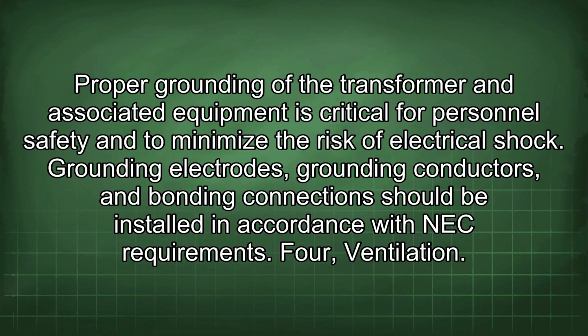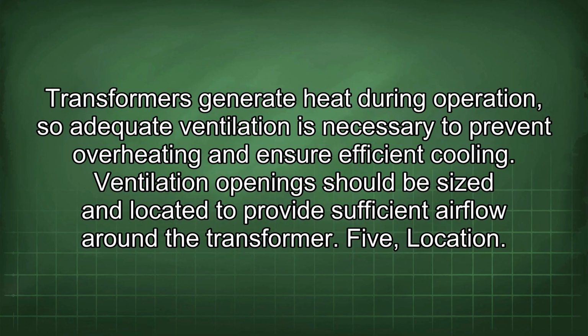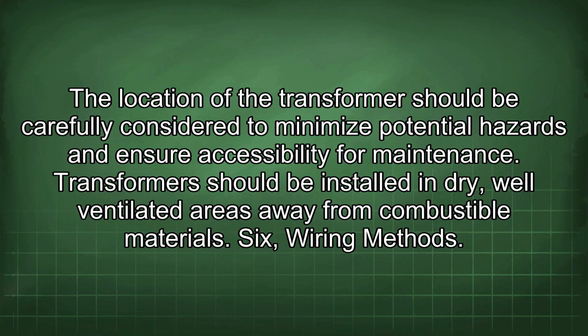4. Ventilation. Transformers generate heat during operation, so adequate ventilation is necessary to prevent overheating and ensure efficient cooling. Ventilation openings should be sized and located to provide sufficient airflow around the transformer. 5. Location. The location of the transformer should be carefully considered to minimize potential hazards and ensure accessibility for maintenance. Transformers should be installed in dry, well-ventilated areas away from combustible materials.